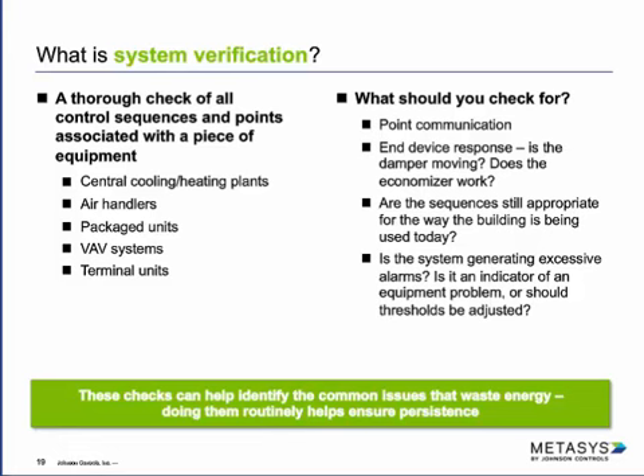A thorough review makes sure these things are implemented and that someone hasn't overridden them or put them in manual mode. If you think it's working one way but someone's overridden the sequence, you're not achieving the energy savings or persistence you expect from that equipment. Finally, excessive alarms are a common problem. With the sheer amount of data coming in, alarms can be overwhelming to the operator trying to weed out what's really a problem versus what's just a threshold set too tight. Looking at those alarms, we identify which are real problem areas and which thresholds need adjusting, so we catch critical alarms without having so many that we're just acknowledging them all and missing potential problems and energy wasters.